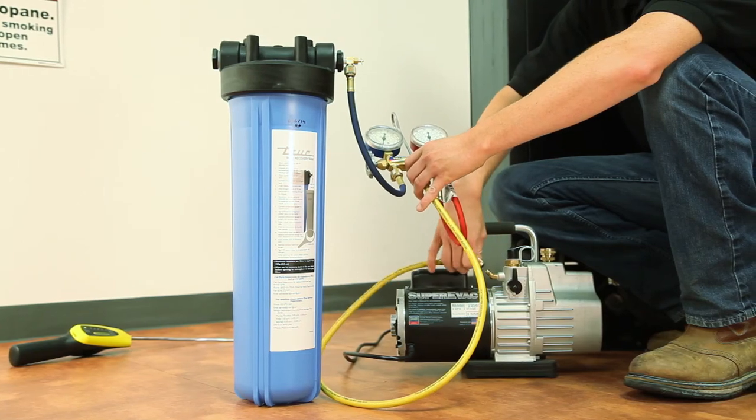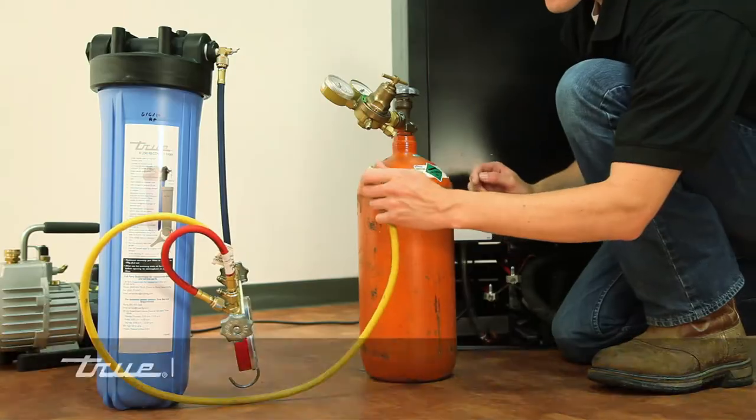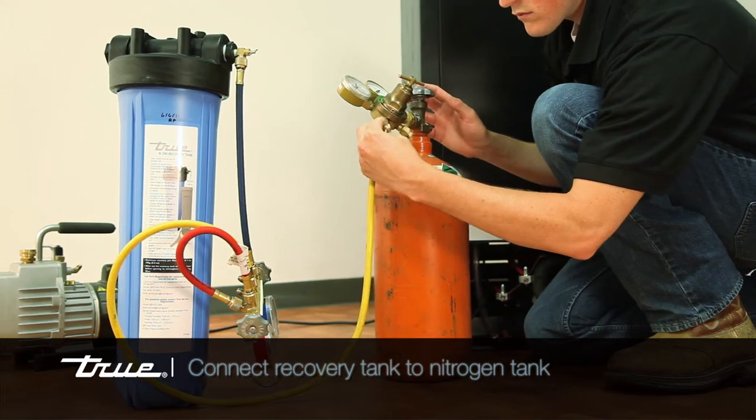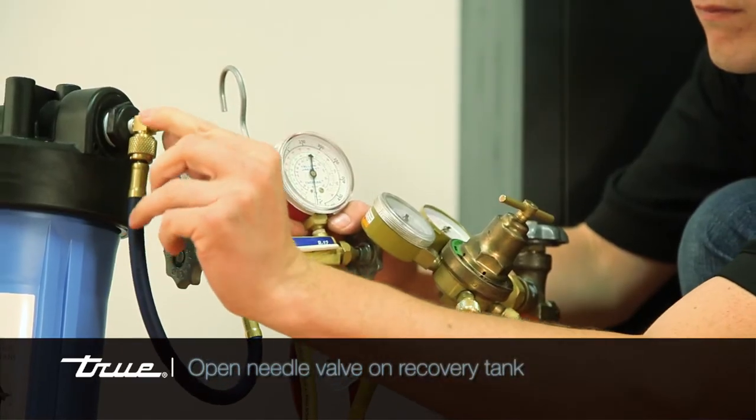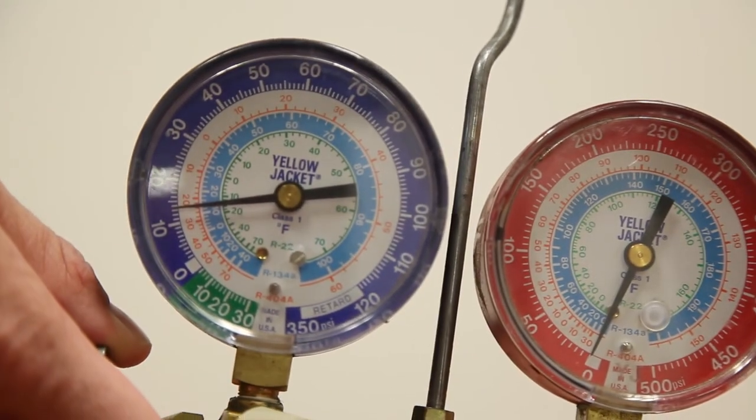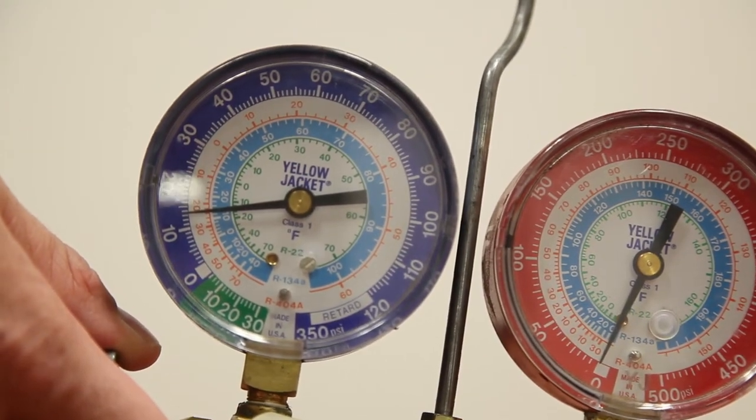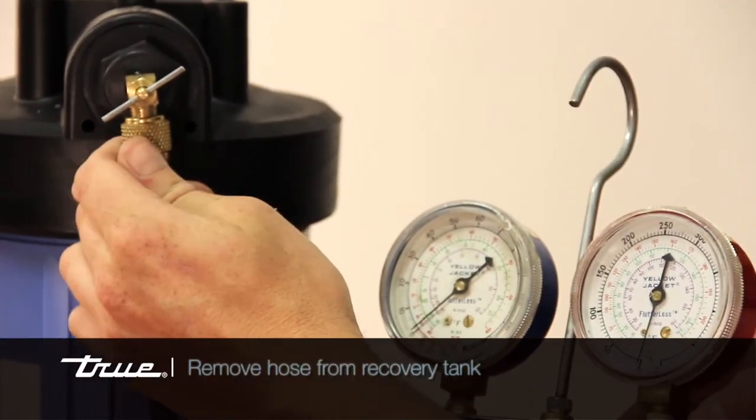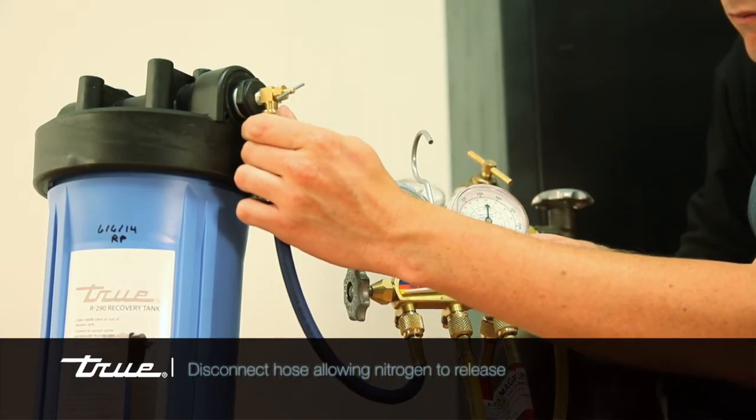Disconnect your gauges from the vacuum pump and connect to your nitrogen tank. Open the needle valve on the recovery tank. You will then break the vacuum in the recovery tank by adding 13 pounds of nitrogen into the tank. The next step is to remove your hose from the tank and release the nitrogen from the tank.